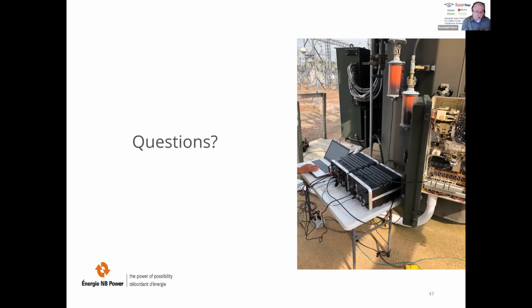What is the relationship between vibration, dynamic resistance, and motor current? Looking at the past, in 2008, 2009, we started just with the vibroacoustic and the motor current. The motor current, as I said in the beginning of the presentation, helps us to start and record and stop the recording. And second, it gives good information on whether the motor works properly or not, just by measuring the current. If it forces, there are some problems. So this is the first.